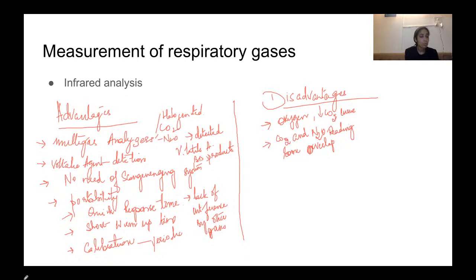And if the analyzer is set to measure a volatile agent different from the one present in the mixture being analyzed, it won't detect it. These are analyzers where you need to set the agent being monitored; if you switch the agent, it will not detect that agent. Now, interference from substances like ethanol, methanol, dimethyl ether, acetaldehyde or acetone can cause high volatile agent readings. These analyzers also help to detect volatile agents, so when a volatile agent is being used, they can show a high reading if there is some contamination with ethanol, ether, methanol, methane, etc.